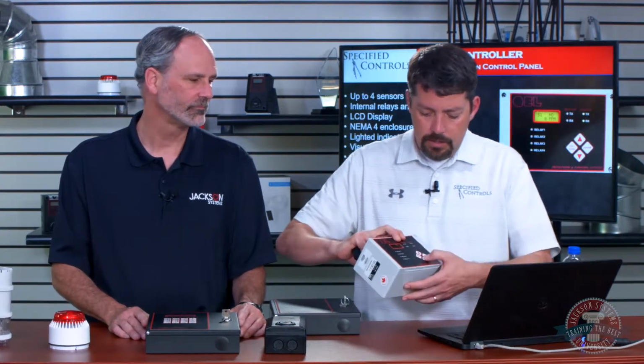Right. So the Q4C panel, 4 is in the name, 4 sensors. It's basically exactly the same. Internal relays, outputs, LCD display. This is a NEMA 4 enclosure as well. Uses the same software. The only other thing is, this one does have buttons. The refrigerant monitor doesn't. You have to use the magnet. Okay, so essentially, there you go. It's a very simple panel. Virtually the same panel, just smaller and in a little bit different enclosure.